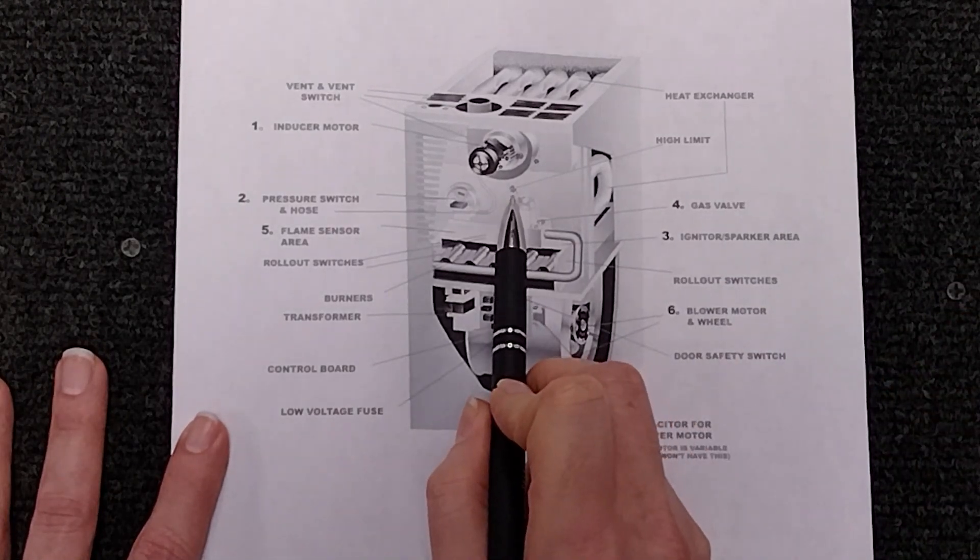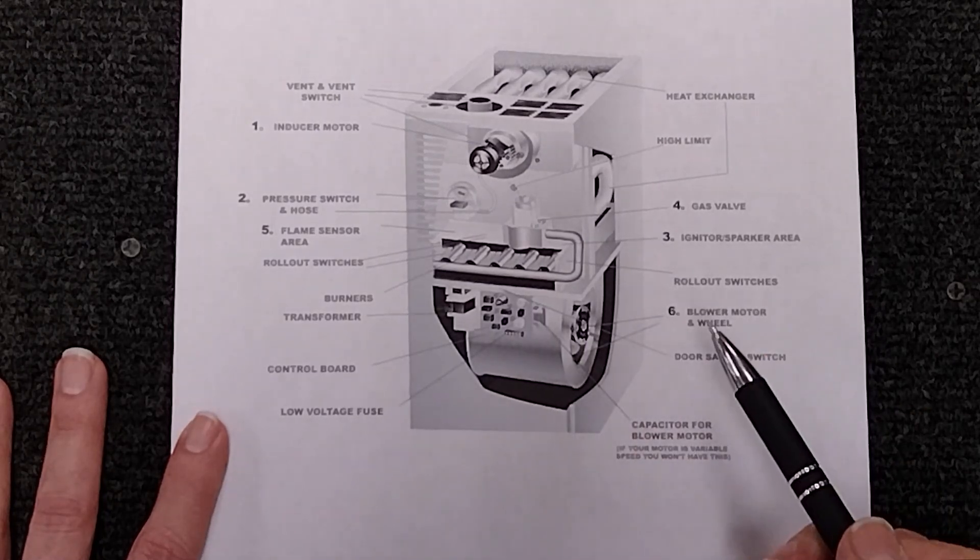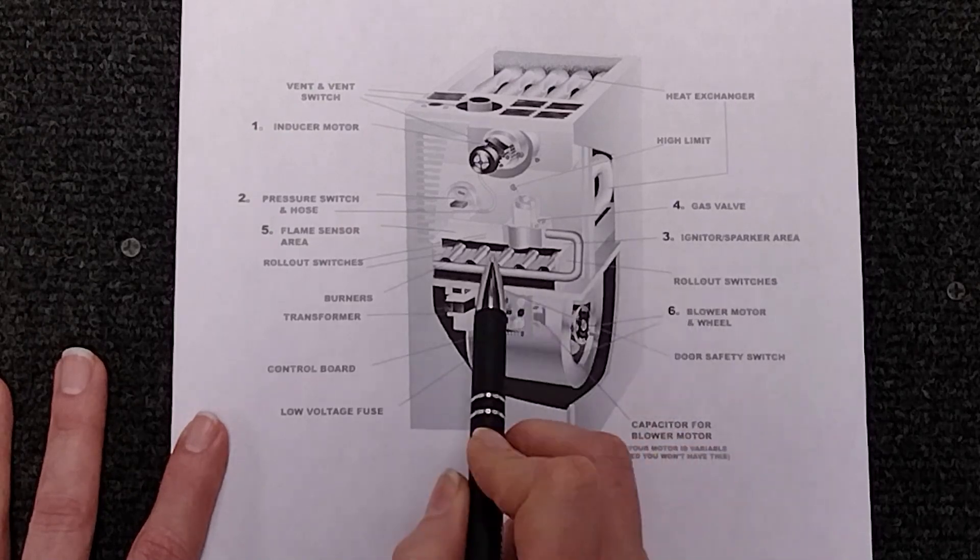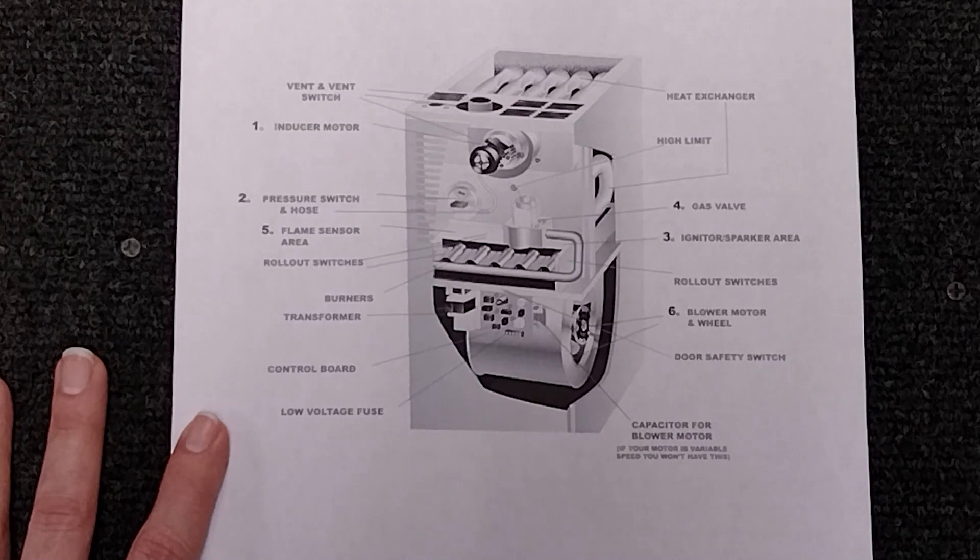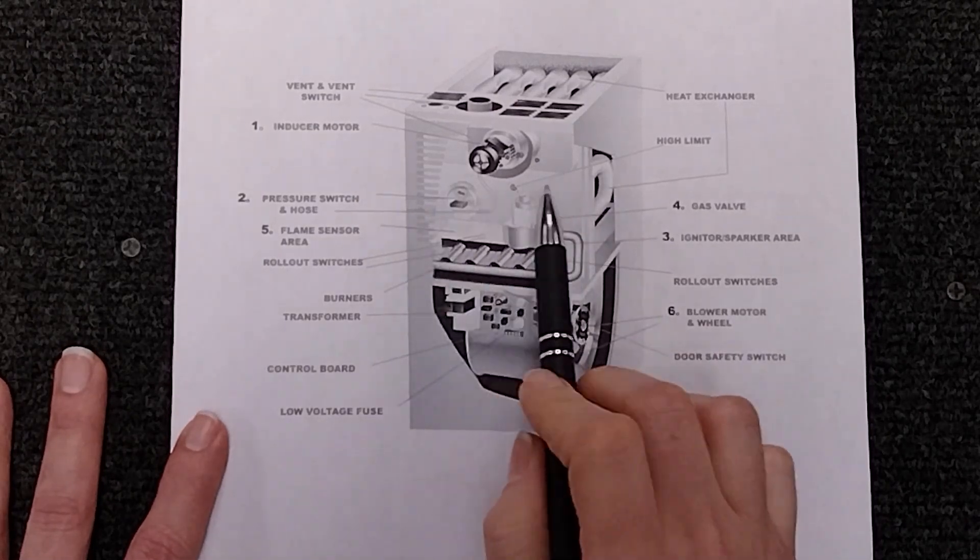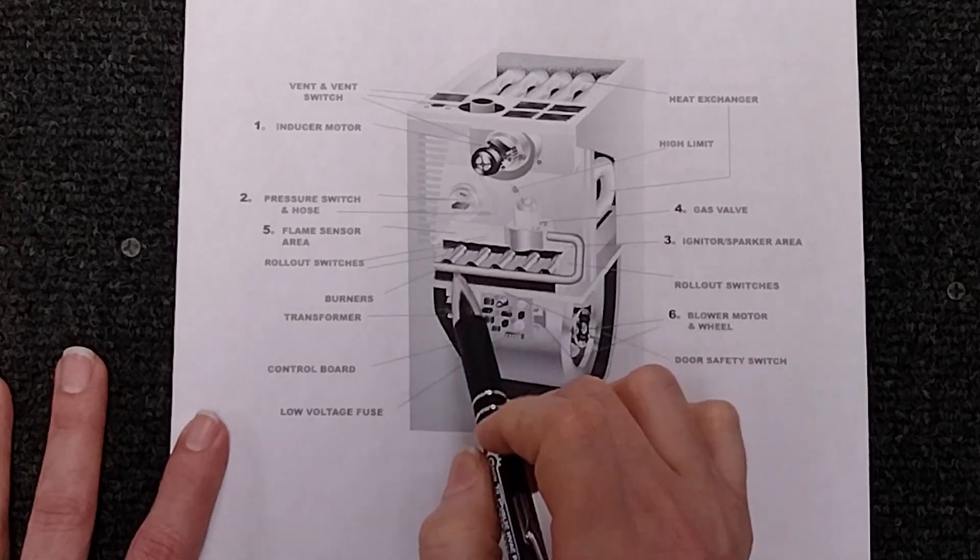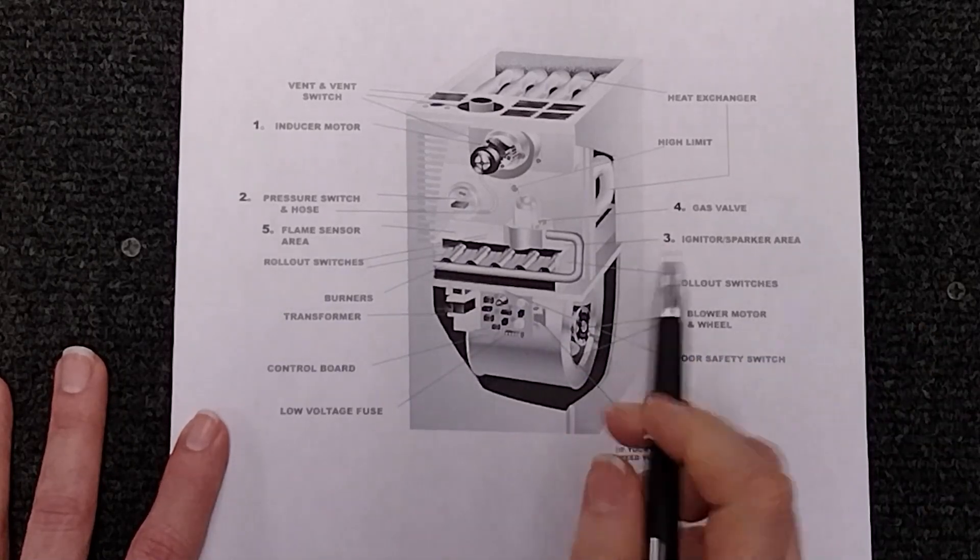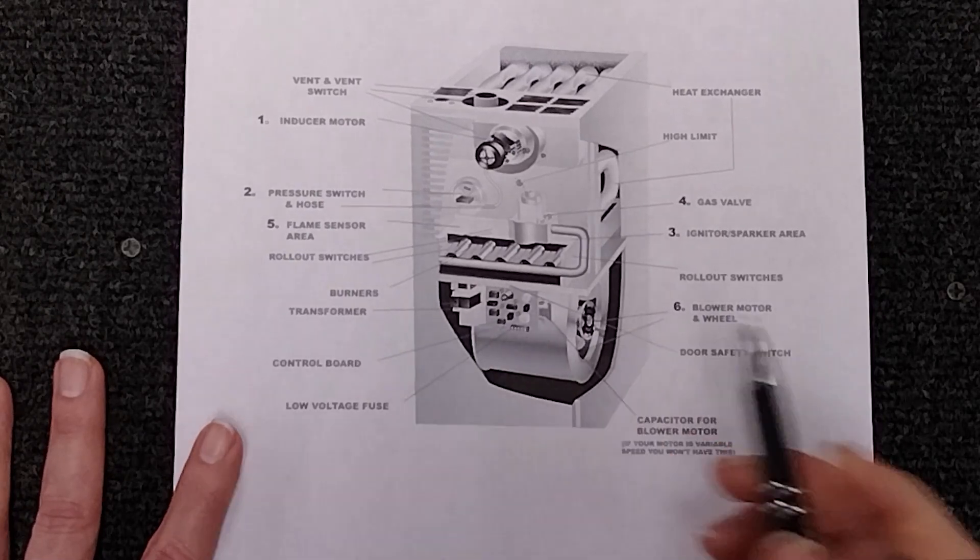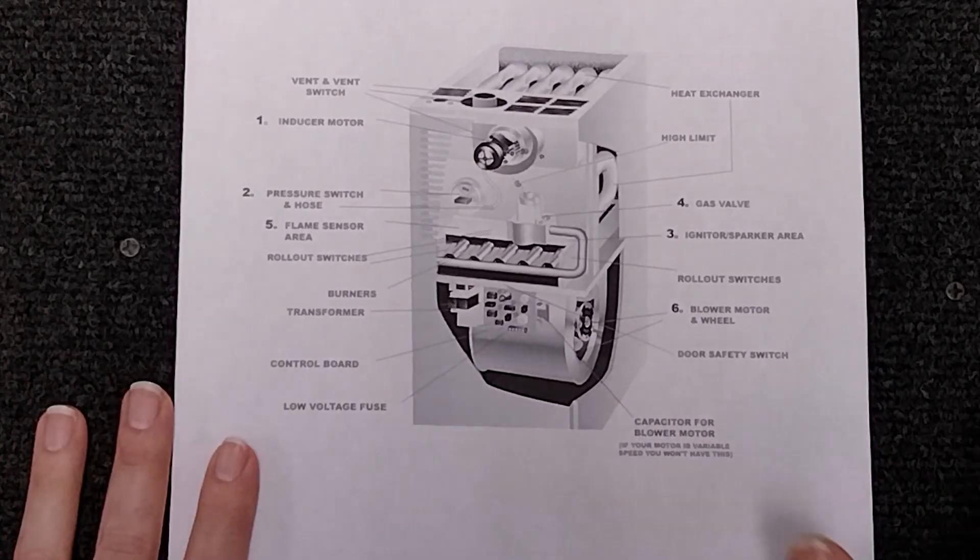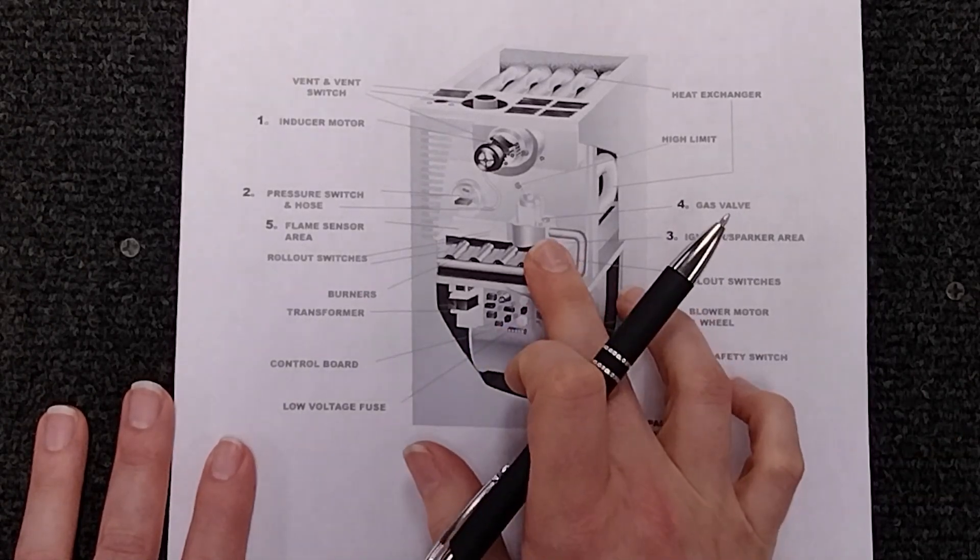Your high limit, your limit switch, sometimes they'll be on your blower. You have rollout limit switches on your burners that are manual. And once it goes and most people their limit switches are in line so it has to go through all of these limit switches before it gets to the point of your control board sending power to your gas valve.